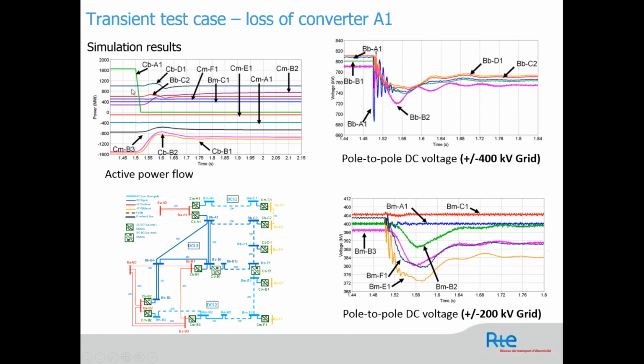Another comment I can make here is that the outage is made at 1.5 seconds, and at 1.8 seconds, in less than 300 milliseconds, the DC grid is already stabilized, so it's quite fast. On the DC voltage, you will see some transients. These transients are related, of course, to the cables, lines, combination of cables, combination of lines, and also to the frequency impedance of the grid of the station. So you can see some harmonics here, which are quite predictable, but at the same time the system is still stable.